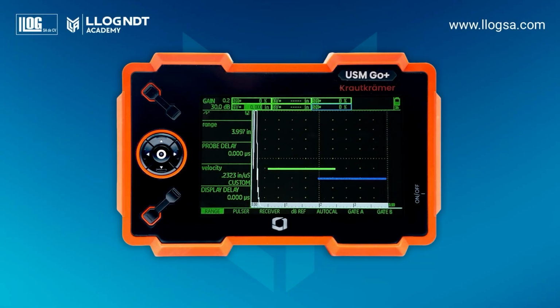Angular beam standardization. For the standardization with an angular beam, we will use the IIW Type 2 block and a 2.25 MHz transducer with a 70-degree wedge. We make the following adjustments. Range, 10 inches. Probe delay, 0. Select the velocity corresponding to shear waves in steel. Display delay, 0 microseconds. Set voltage and energy to high. Damping, 1000 ohms. Pulse repetition frequency, auto high.